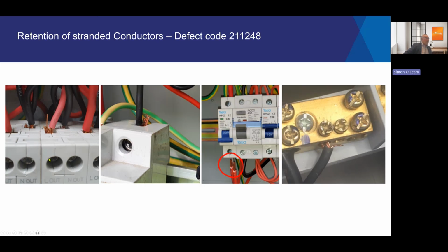So as we can see in this diagram, we've got strands that are sticking out or have escaped the terminals. In this, the whole set of conductors in the bottom of, possibly, the main switch have come away. And here one of the strands hasn't even entered into the terminal in the first place. So it's quite important that we terminate correctly, for a number of reasons. Stray strands can cause short circuits. They can reduce the current carrying capacity of the cable or allow terminals to loosen over time. And going back to manufacturers' installation instructions, a lot of them will tell you certain stripping lengths of conductors to go into the terminals as well.